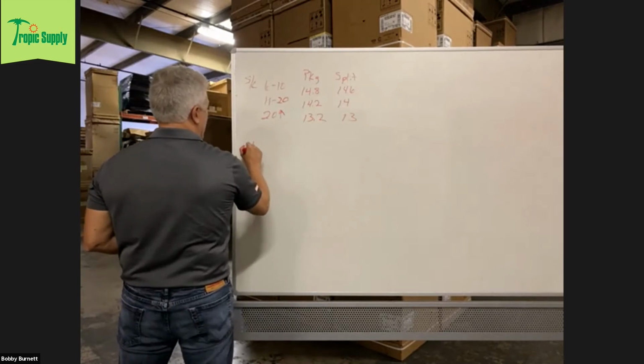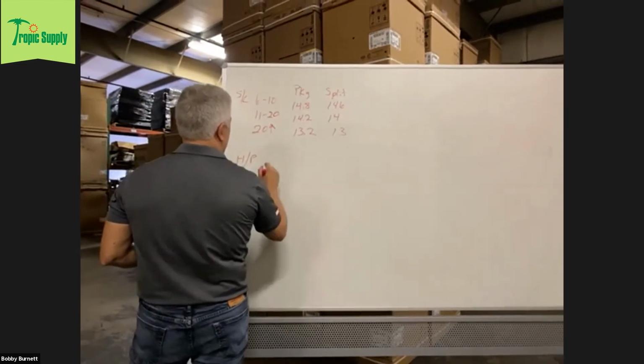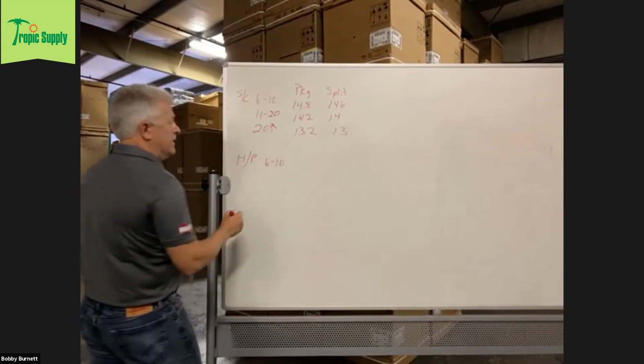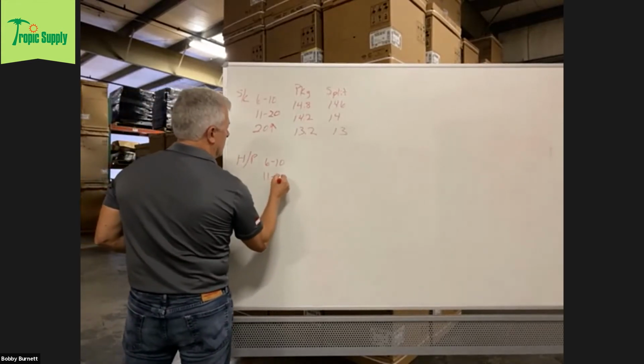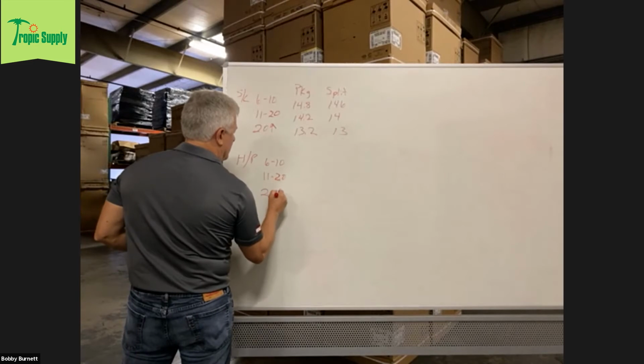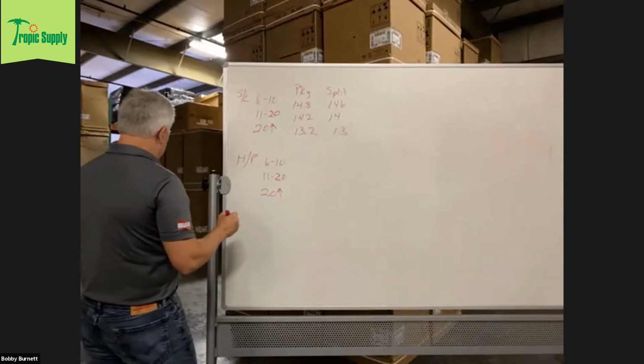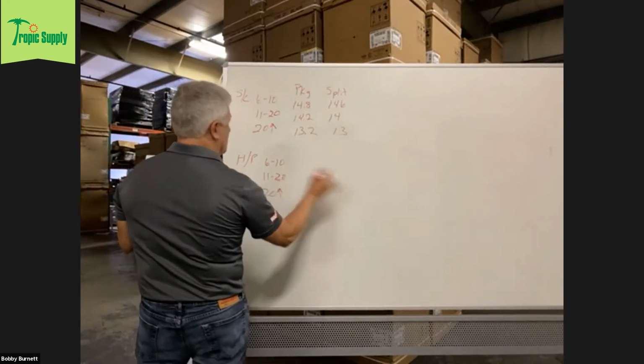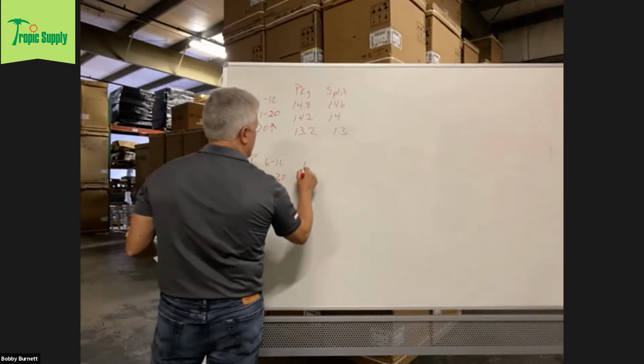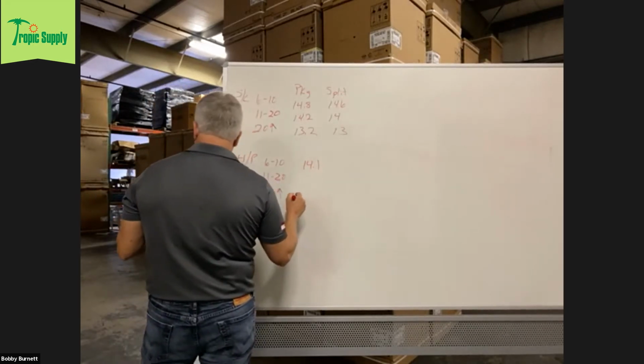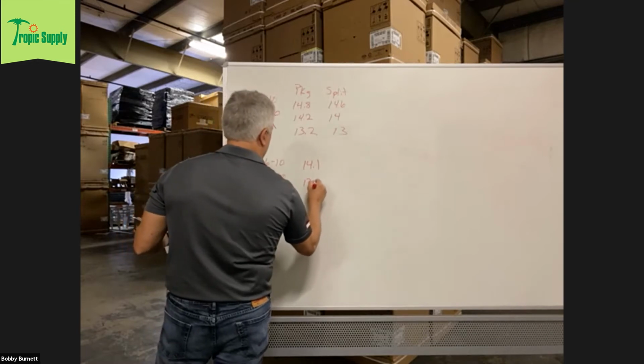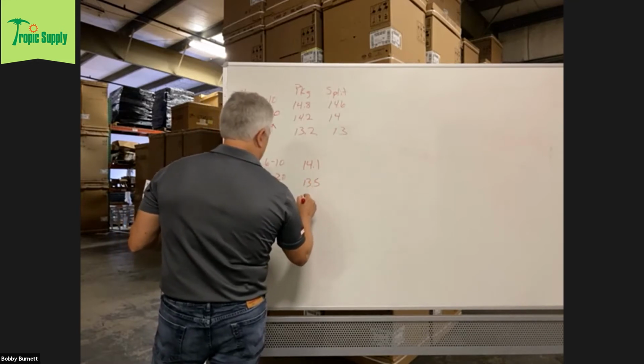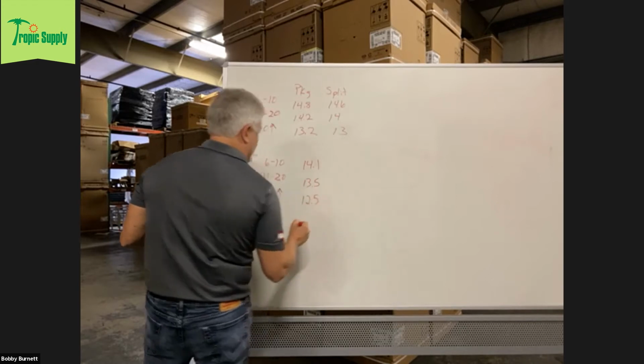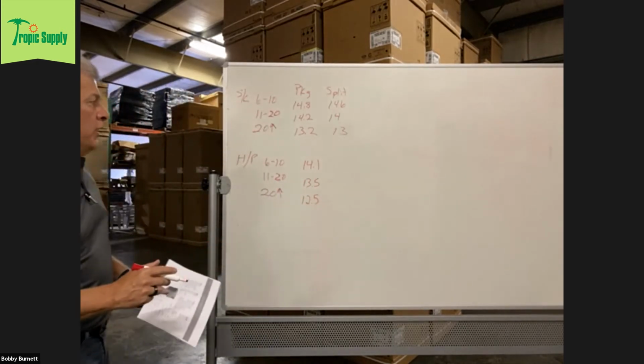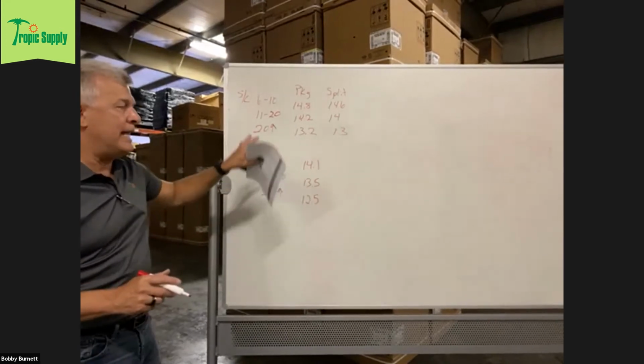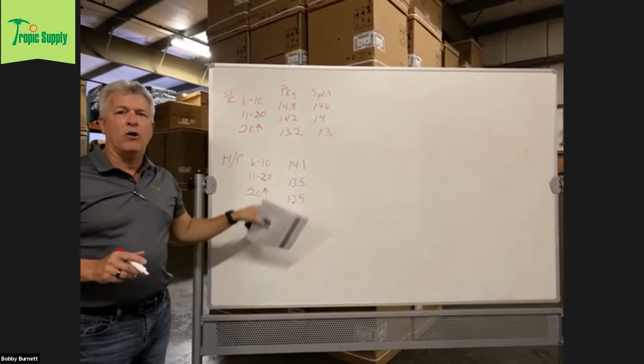And then they have it broken down on the heat pumps. Same thing on the heat pumps: 6 through 10, 11 through 20, and 20 and up. It doesn't matter if it's package or split on those, it's going to be a 14.1 IEER, a 13.5 IEER, and a 12.5 IEER. Remember, this is an average of different EER ratings.